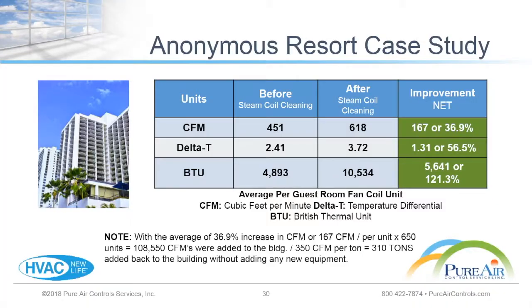Another example, looking at smaller hotel room units, where we did our restoration process and measured before and after CFMs, before and after delta T. We can go into this more individually, but the bottom line on this particular resort - a 600 to 650 room resort - by virtue of increasing the efficiency of their air handlers, we were able to add 300 tons of air conditioning through this process. That's all verified through the study. Really, really big improvements from a straightforward process of restoration and cleaning.